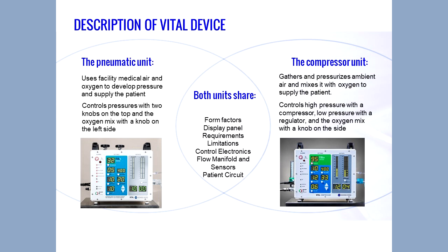A pneumatic ventilator basically takes oxygen and air from a hospital resource, meaning that it provides both oxygen and air under pressure, 50 psi nominal pressure. This pneumatic ventilator doesn't have an internal engine, motor, or blower. It simply transduces the pressure coming from the hospital's wall-mounted resource of both oxygen and air, which typically exists in most hospitals.